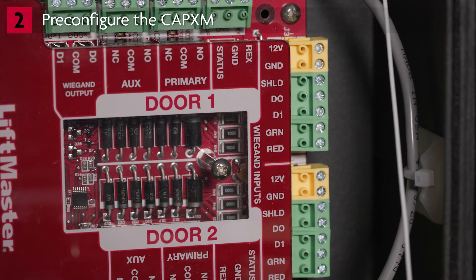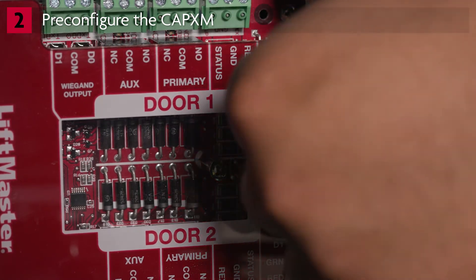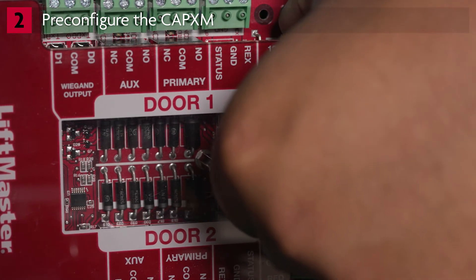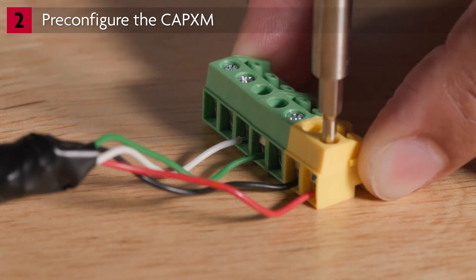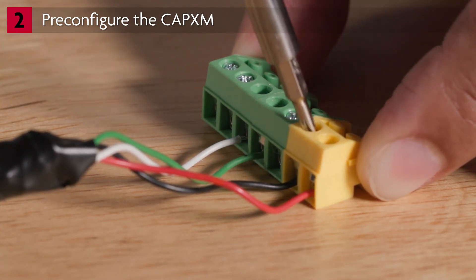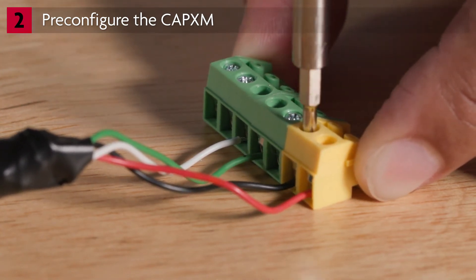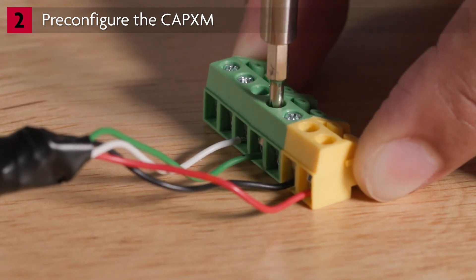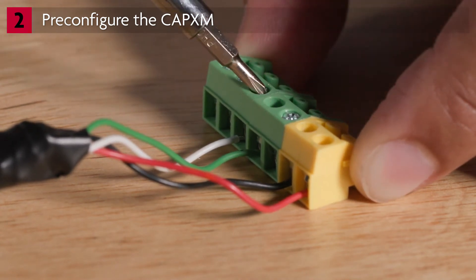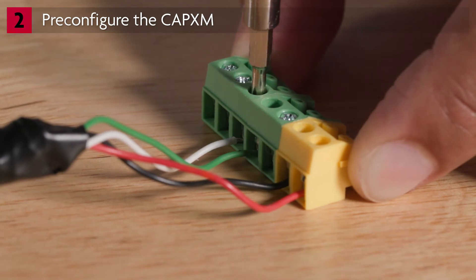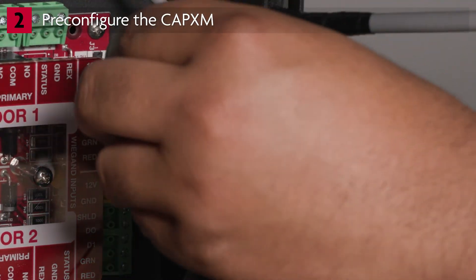We will demonstrate connecting the reader to door 1 of the door board. Remove the yellow-green terminal block from the door control board. Connect red to the 12VDC connector, connect black to the ground connector, connect green to data 0, and connect white to data 1. Reattach the terminal block. If there are any other devices you wish to test, connect them now according to the instructions in the manual.